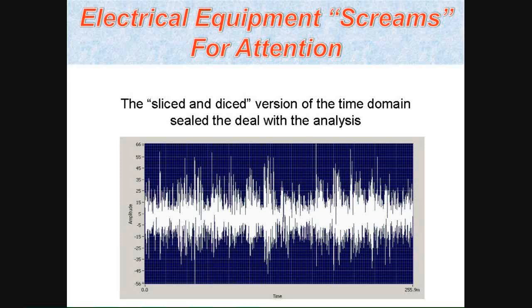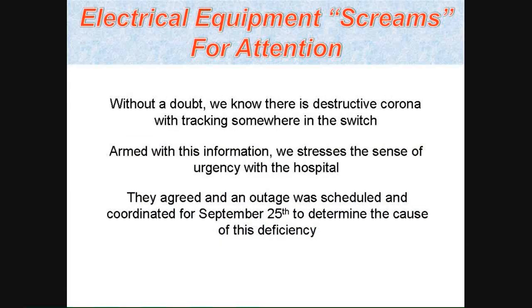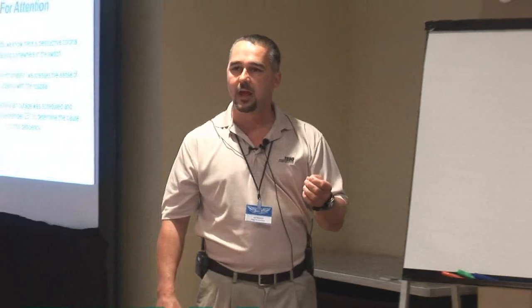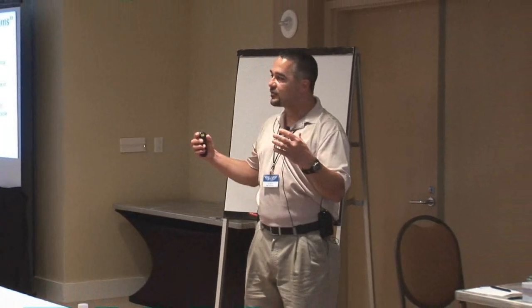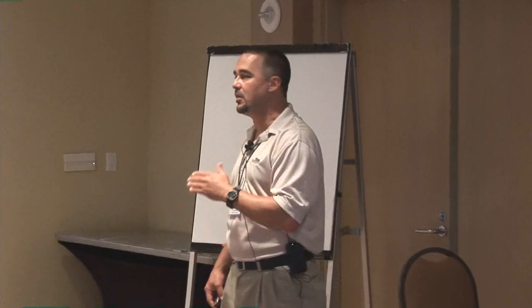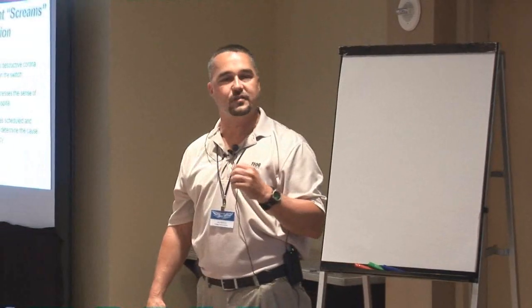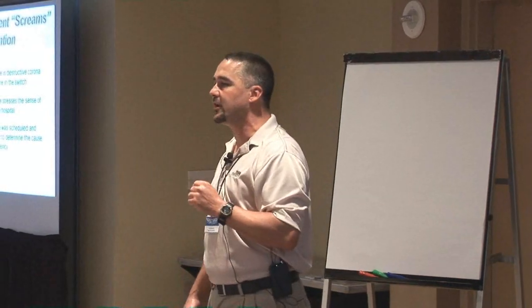You can see the excursions are much higher. They're far more compacted, meaning the discharges are occurring more often and at greater intensity levels. Without a doubt, it becomes tracking. And as part of, you guys have heard it called destructive corona. And with anything over 1,000 volts, I don't need to tell anybody, you have an ionization process taking place where a high frequency noise is created, but it's very predictable. And it's predictable because the stresses create that ionization, and it occurs every 16 milliseconds. So the FFT looks real nice with the 60 hertz harmonics. The time domain is very linear and uniform.